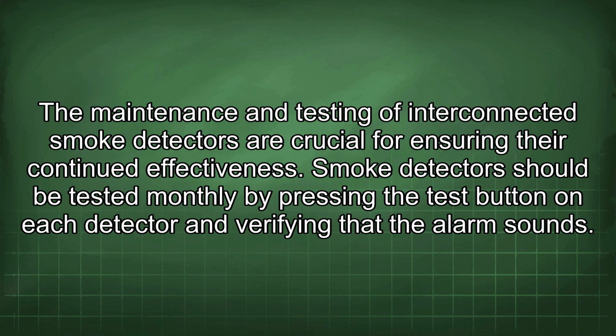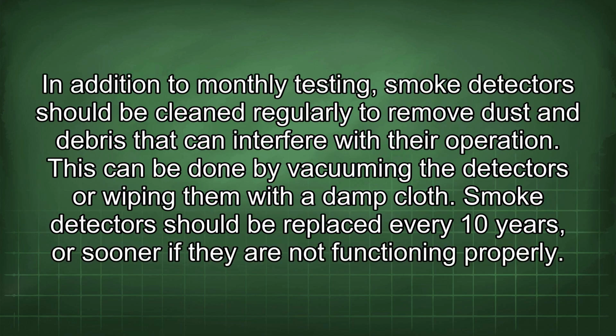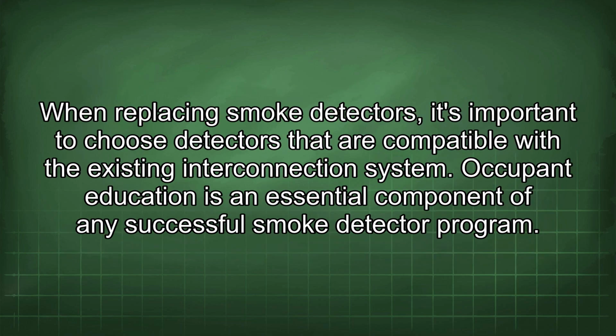manufacturer. The maintenance and testing of interconnected smoke detectors are crucial for ensuring their continued effectiveness. Smoke detectors should be tested monthly by pressing the test button on each detector and verifying that the alarm sounds. In addition to monthly testing, smoke detectors should be cleaned regularly to remove dust and debris that can interfere with their operation. This can be done by vacuuming the detectors or wiping them with a damp cloth. Smoke detectors should be replaced every 10 years, or sooner if they are not functioning properly. When replacing smoke detectors, it's important to choose detectors that are compatible with the existing interconnection system.